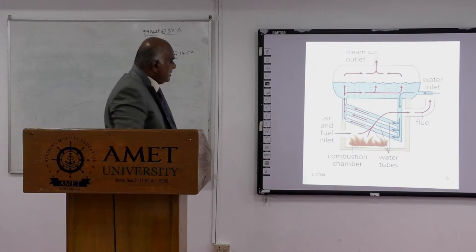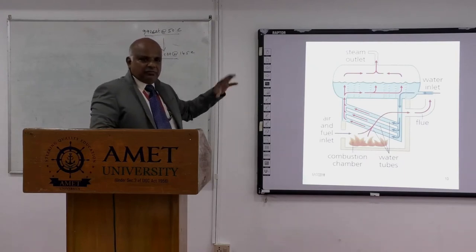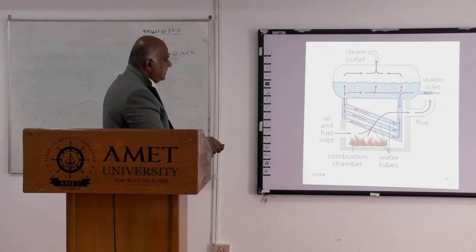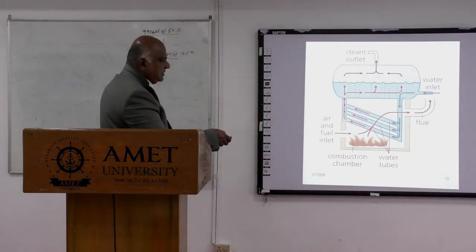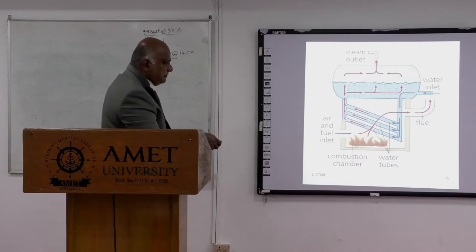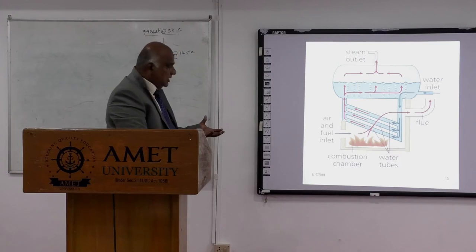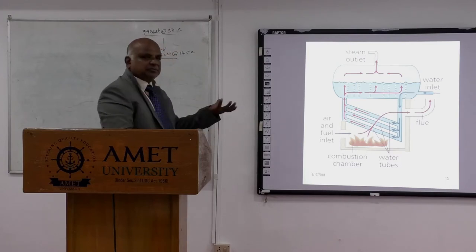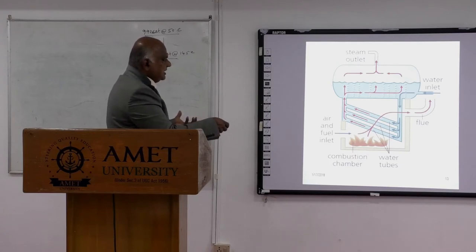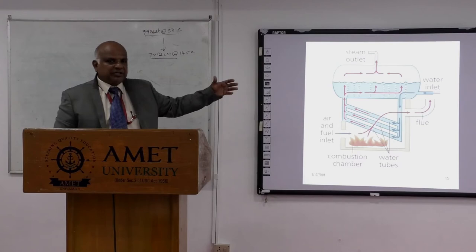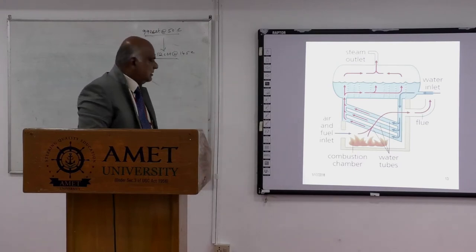In the next stage of boiler design, feed water enters the steam drum or water drum, passes down via the downcomers, flows through the tubes, and as it is heated by the hot flue gas it vaporizes and rises. The lighter steam collects in the upper steam chamber and is utilized in various places. There are 14 listed uses of steam.